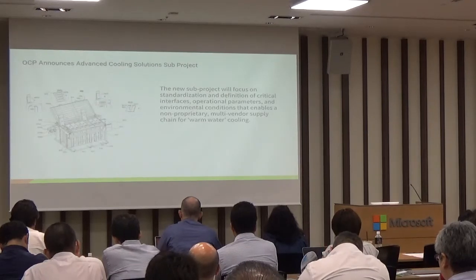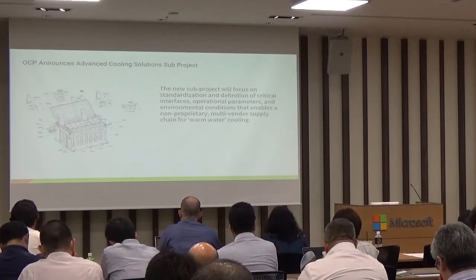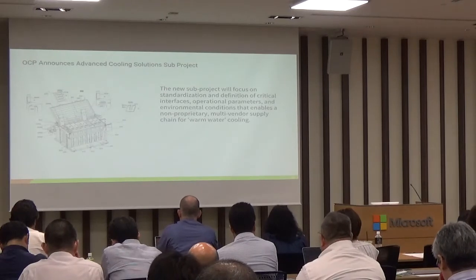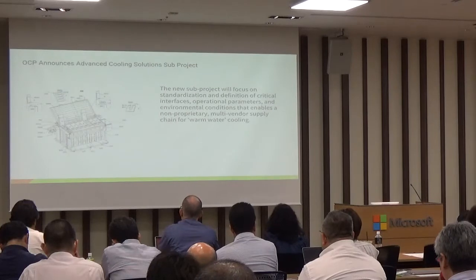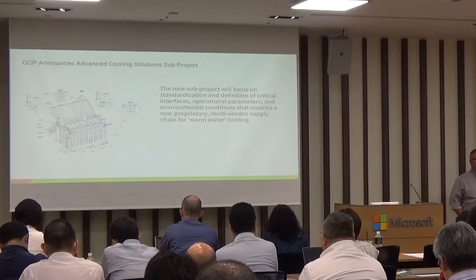First would be cold plate technology. It's liquid cooling using cold plates inside the IT equipment, manifolds on the back of the rack that distribute cold water or warm water, and then return that to the chillers or the cooling towers outside the buildings.